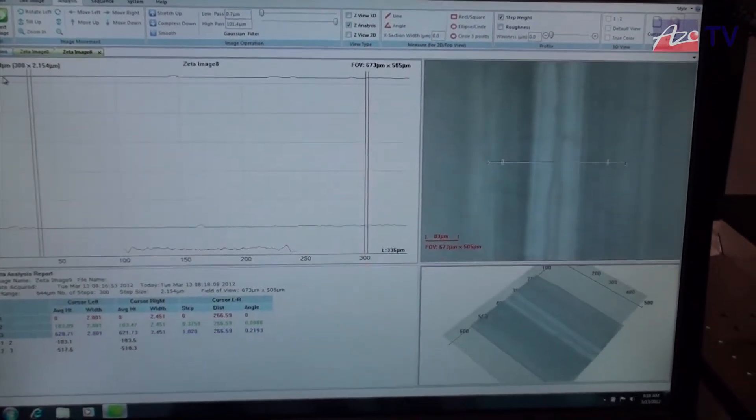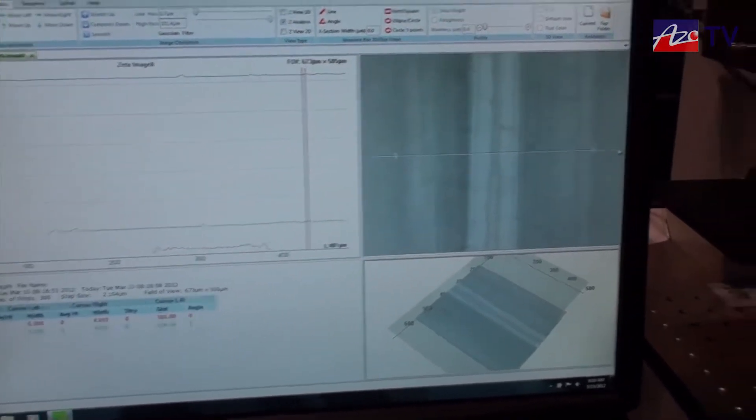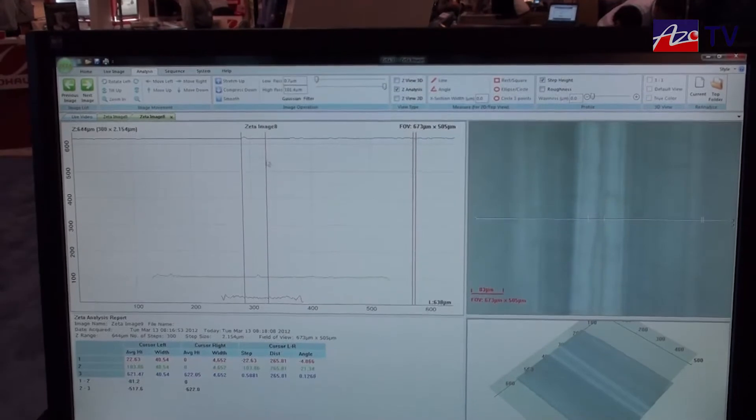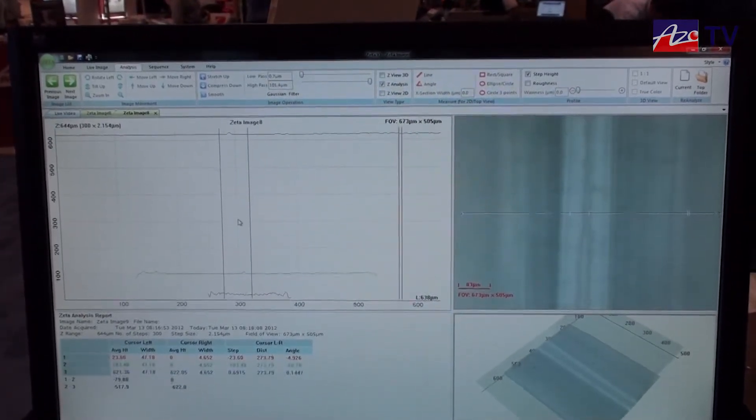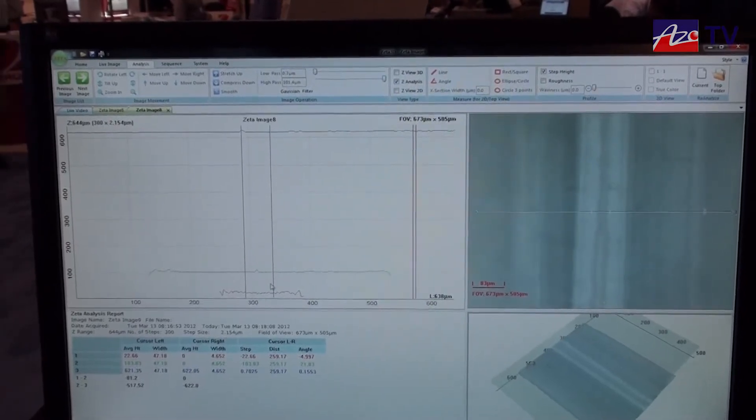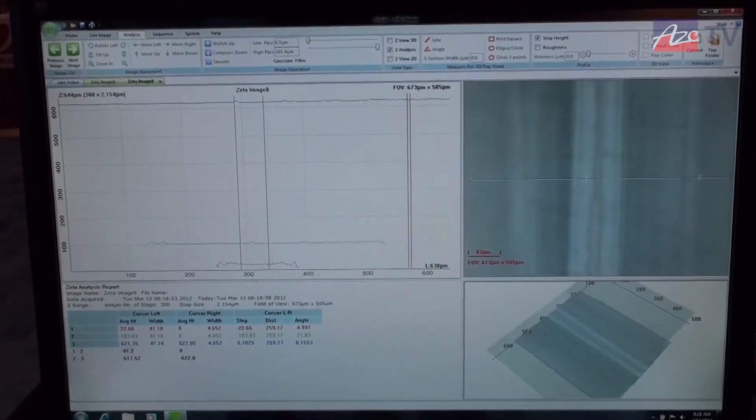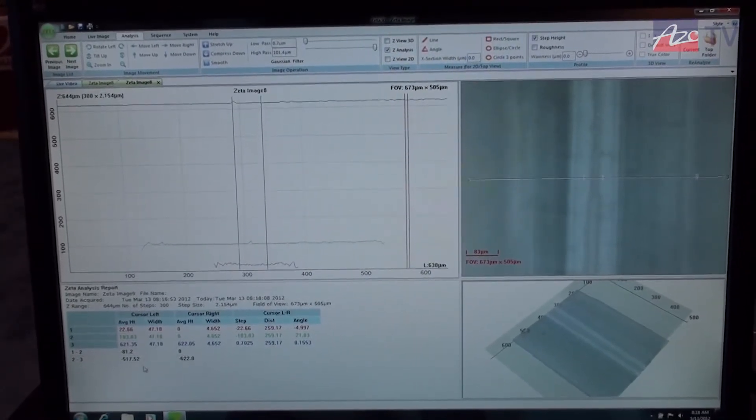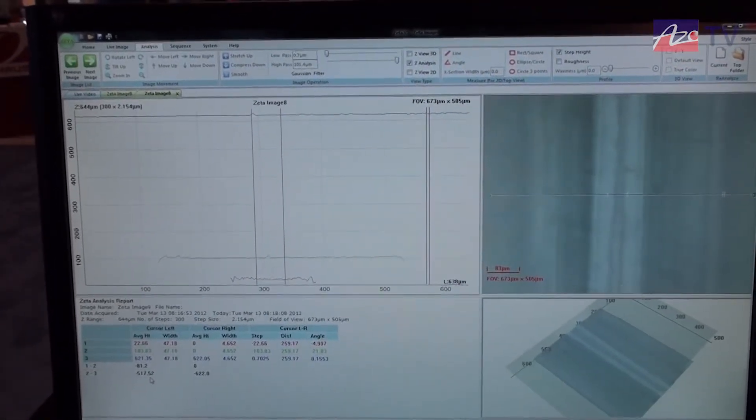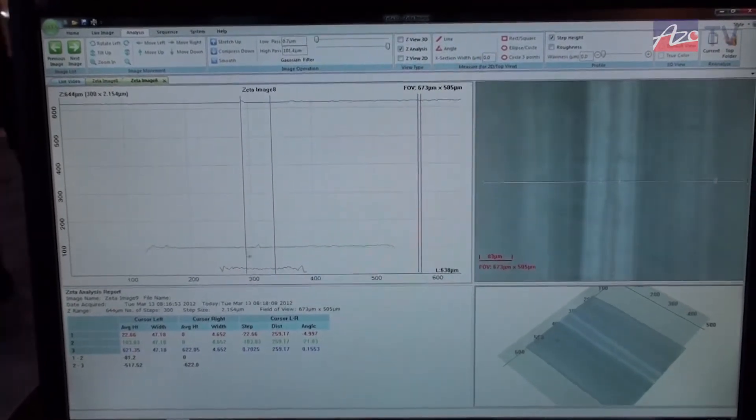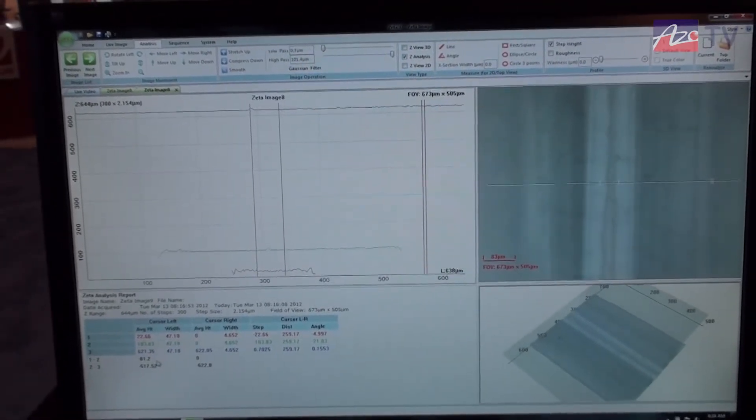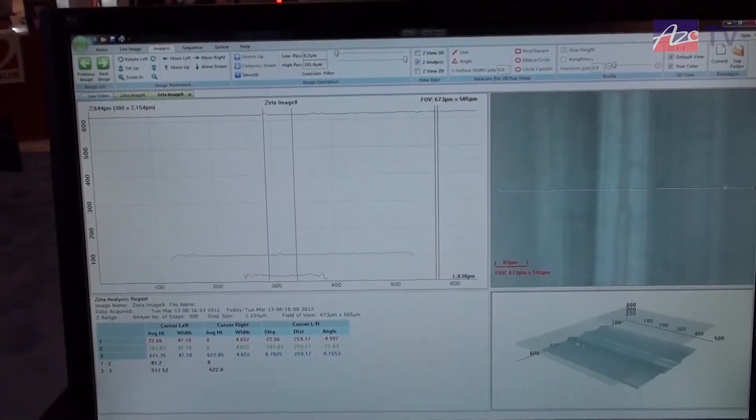We'll look at that dataset now that I've processed it. And what you'll notice is that per the cross section, I actually have three individual heights. I have a height from the top to the middle to the bottom. So if I look at this cursor set, it allows me to average all the information for the heights that we've just collected in the Z-Stack all the way in between. In this particular measurement, I have a distance from the top to this layer, which is layers two to three. They're also color-coded. That's basically 517 microns deep times its refractive index. The air gap is literally here in this center section. It is roughly 81 micron channel depth.